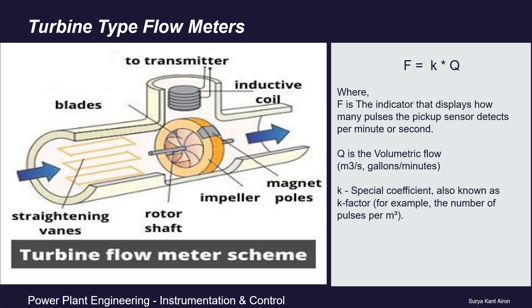The K factor is a key coefficient that displays the number of pulses per unit volume or mass of the medium. This constant value includes the main characteristics of the substance, such as viscosity and temperature, as well as characteristics of the pipe like diameter. It is necessary for the correct display of values in the measuring system. After calibration, this K factor is indicated in the product certificate.